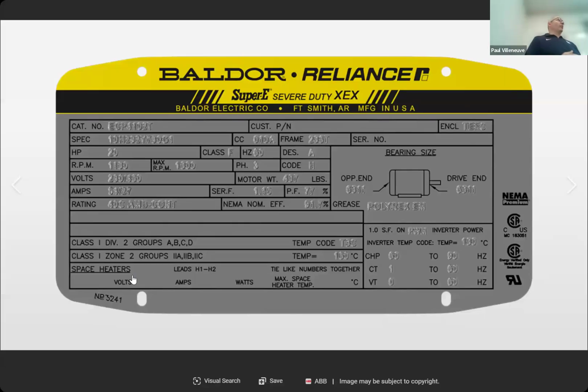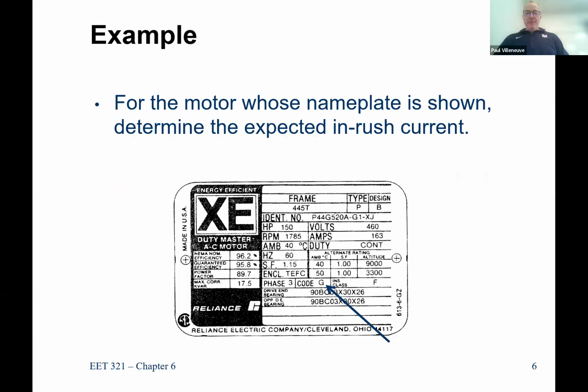So space heaters, you see those for a lot of electrical equipment: generators, motors, breakers. Sometimes you want to keep the cabinets warm because the gas that's in there could get bad. So you keep your cabinets at a reasonable temperature above ambient, and then you don't have to worry about corrosion or electrical insulation because of the water. I think that's all the important stuff there, but let's go back to that kVA code.